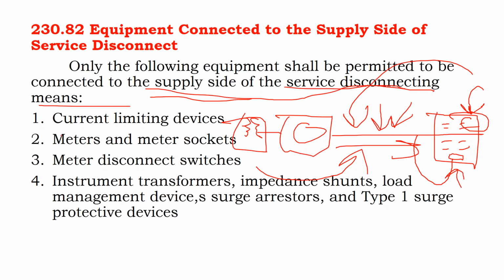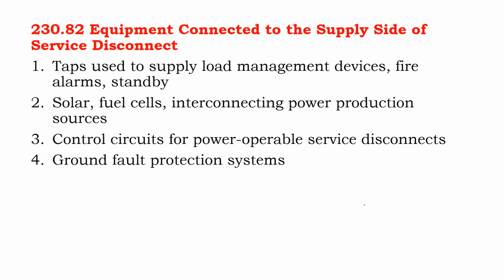Lo and behold, we're allowed to connect certain equipment on the supply side, and that would be energy management devices, meter cans and meter boxes, disconnect switches, load management devices, surge arresters. Stuff that has to do with your on-site electrical generation can be connected to the supply side of your electrical service. That just makes obvious sense. It may not make sense to your local inspector. If you live in a rural area and they've only been doing smaller solar arrays without batteries, maybe the local installer in your area is only doing load side interconnections and not supply side interconnections.